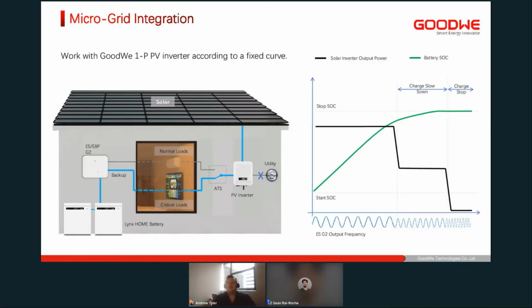Microgrid integration. So this is also quite a new feature with the ES G2. Typically you might have a customer who has an existing grid side PV system installed, and they now want to add some battery capability, whether it's to do some energy arbitrage, or potentially because they need some backup for grid outage conditions.